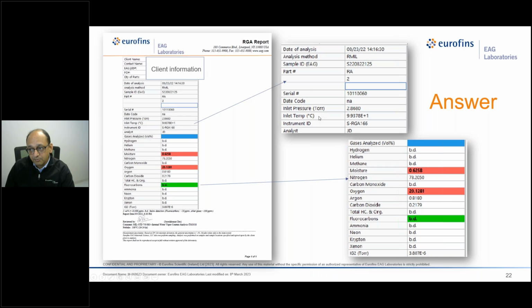But inlet temperature is the temperature where the sample is sitting. Our sample is mounted in a way that the temperature head or a heater is touching the sample directly, and that's where the temperature measurement is done, and that is given as inlet temperature. We also monitor the instrument ID and the initials of the analyst who did this analysis. In this case, it's me. The lower part is where you are most interested, where we are putting the gas analyzed in volume percentage.